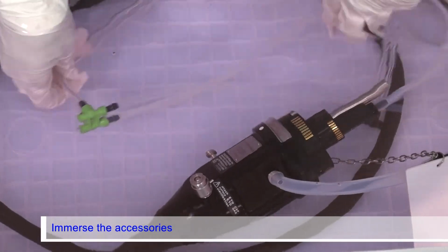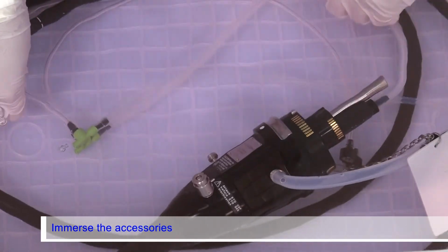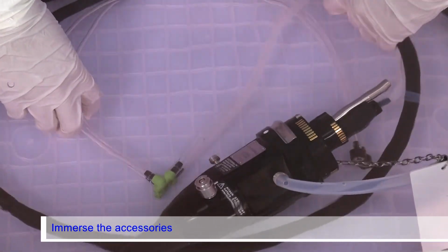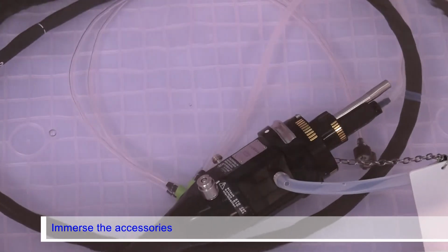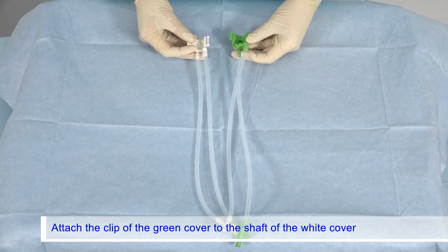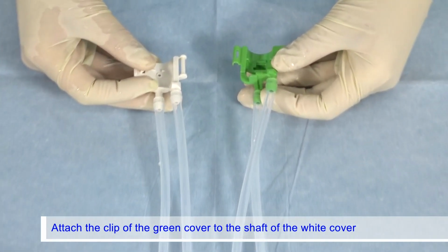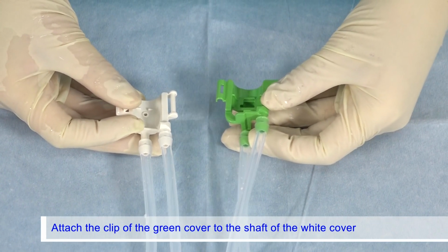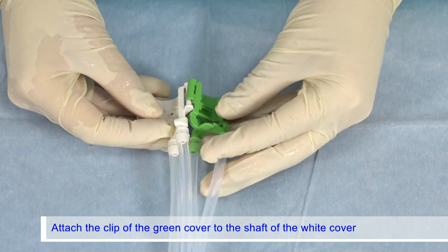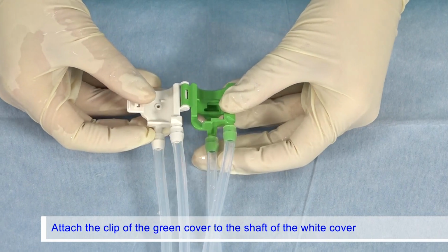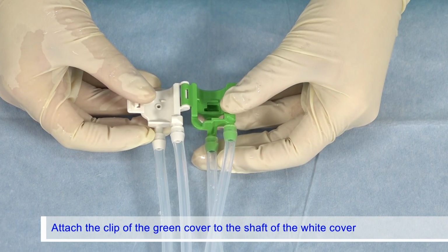Completely immerse the channel plug and the injection tube in the disinfectant solution. Hold the distal end flushing adapter. Attach the clip of the green cover to the shaft of the white cover. Then completely immerse the distal end flushing adapter in the disinfectant solution.